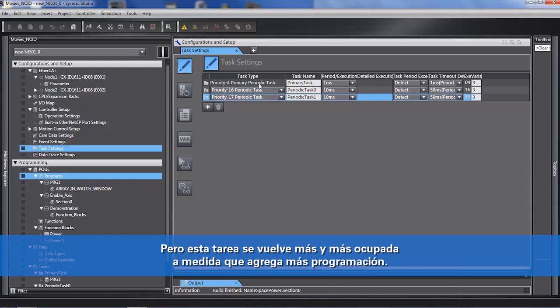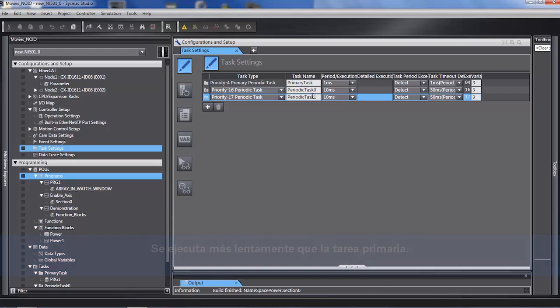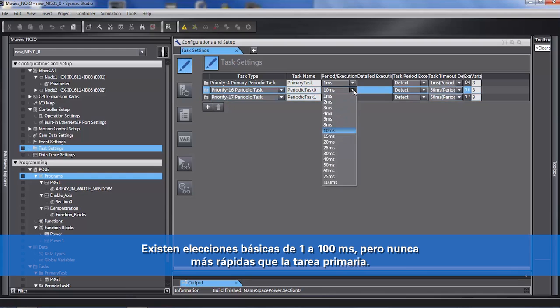What happens though is this task becomes busier and busier as you put more code in it. The secondary place you can put code is in the priority 16 periodic task. It runs slower than the primary task — basic choices of 1 to 100 milliseconds — but never faster than the primary task.